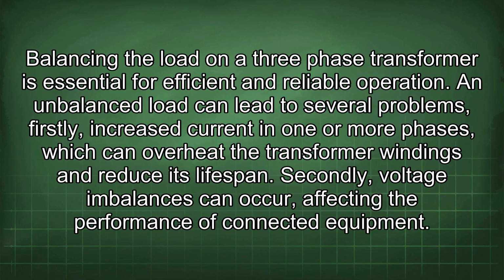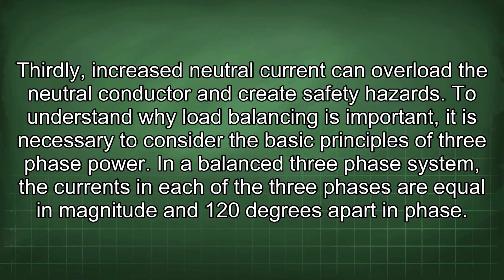Balancing the load on a 3-phase transformer is essential for efficient and reliable operation. An unbalanced load can lead to several problems. Firstly, increased current in one or more phases, which can overheat the transformer windings and reduce its lifespan. Secondly, voltage imbalances can occur, affecting the performance of connected equipment. Thirdly, increased neutral current can overload the neutral conductor and create safety hazards.